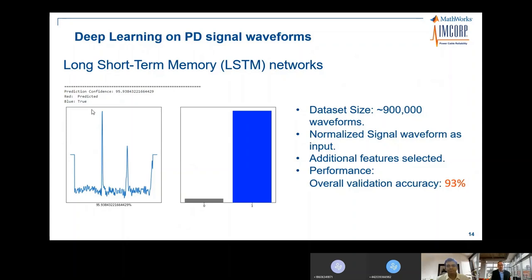The deep learning approach applied a long short-term memory network to partial discharge time series, using the time-domain signal as a feature along with other added features. This model was employed on a pool of about 900,000 human-labeled signal waveforms. The overall validation accuracy is 93%. Deep learning benefits from more data, and studies have been performed on larger pools.